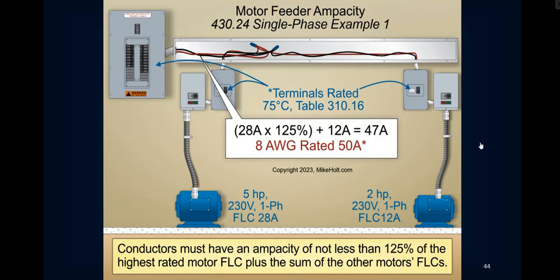You go back to the, and it also, from a question standpoint, they're saying, okay, the terminals in this equipment are rated for 75 degrees. Well, that just told you what column you need to go to in table 310.16, didn't it? 75 degrees Celsius column. We're going to go with number 8 AWG, which is going to be rated at 50 amps.